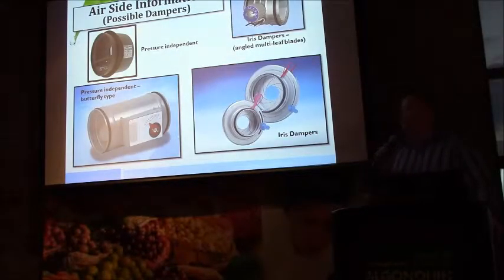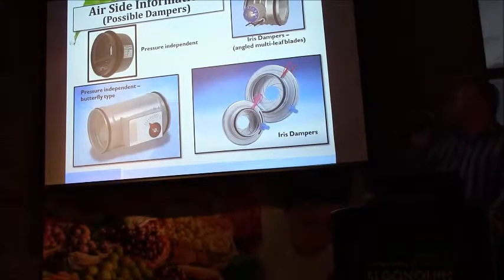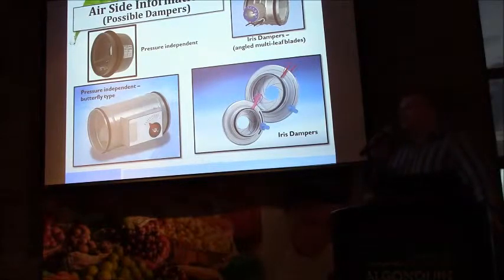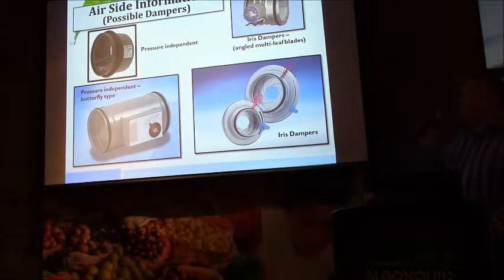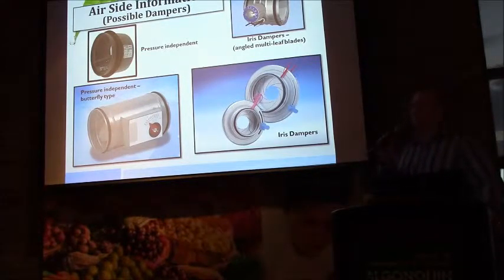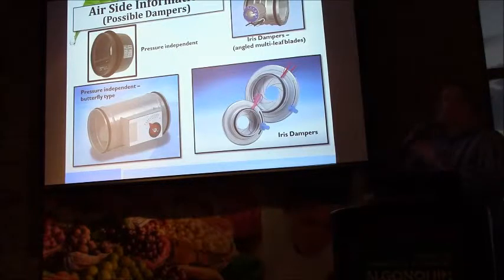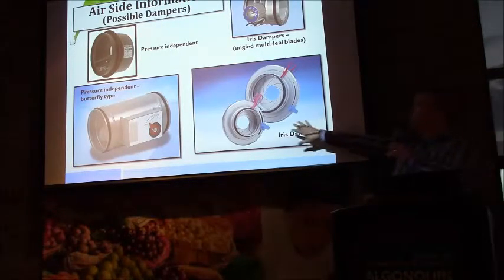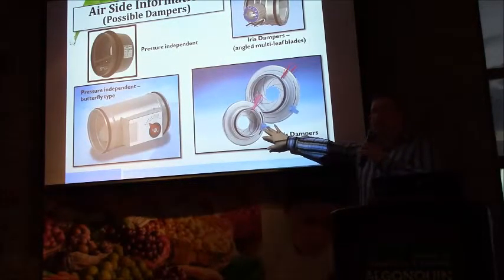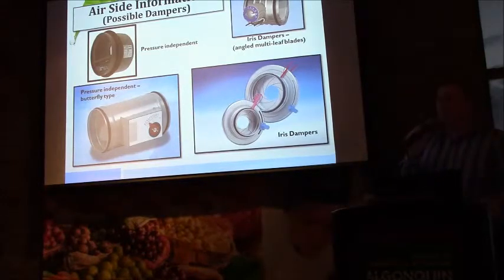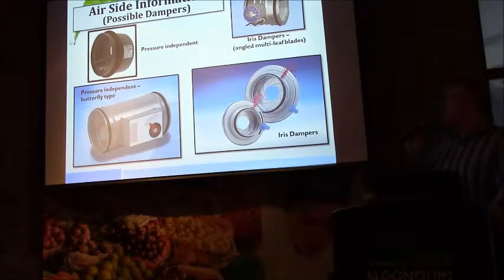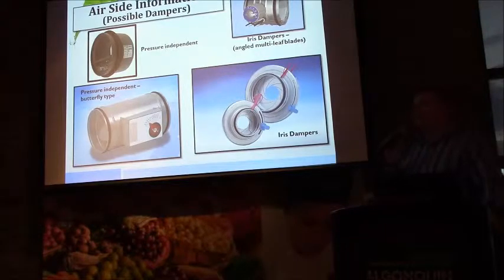And they're generally this first element in the far left-hand corner. These are known as pressure-independent flow regulating dampers. They're installed directly in the duct, and they react dynamically with changes in pressure of the duct system to distribute air into the space in the neighborhood of 5 to 10% accuracy. Failing that, a more traditional approach for a constant volume system might include an iris damper. And the reason that these have benefit is that they're very accurate.